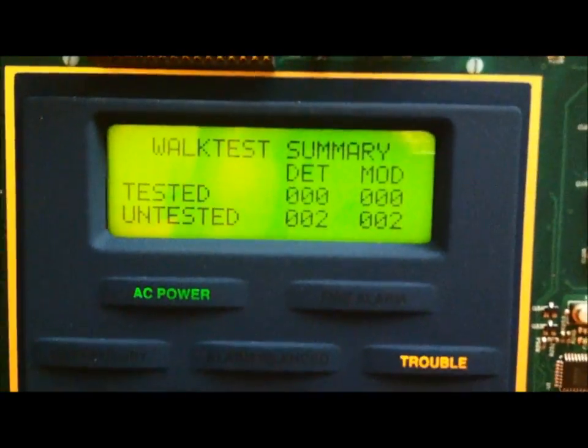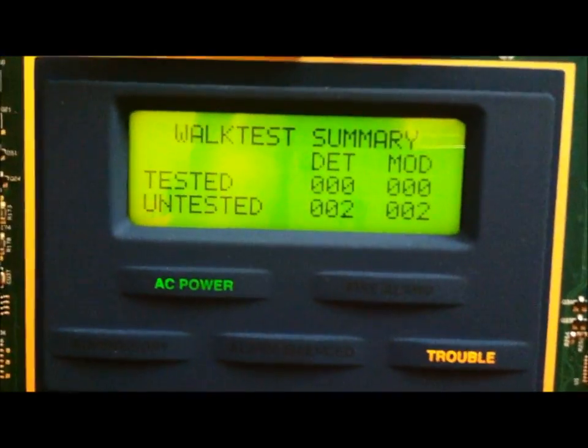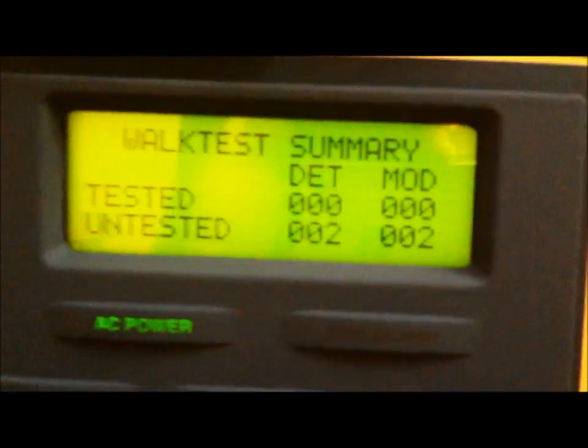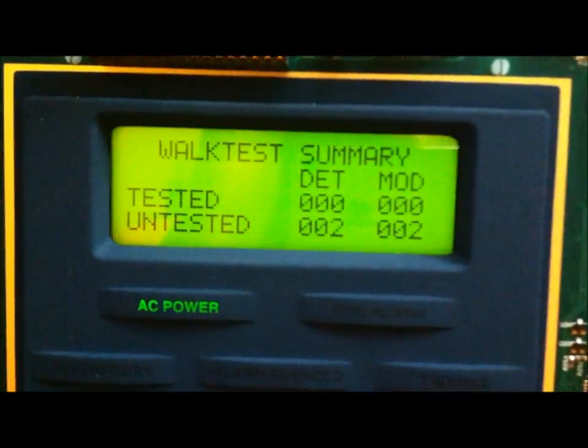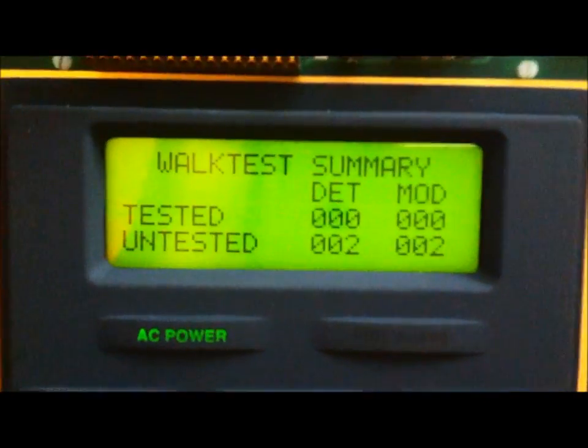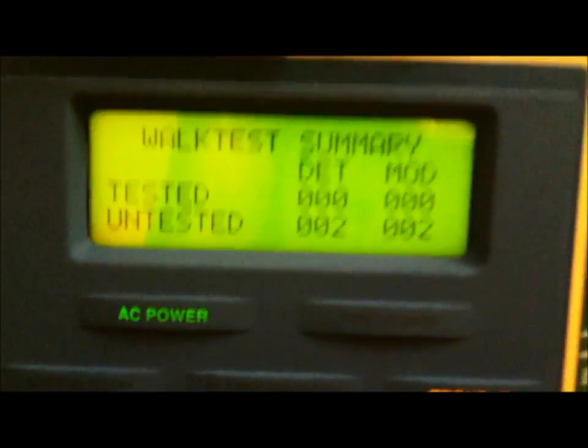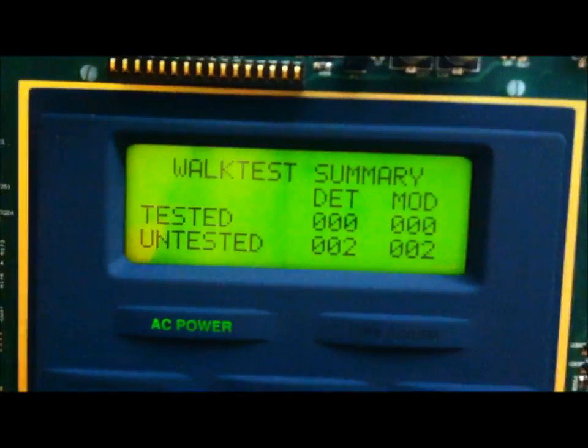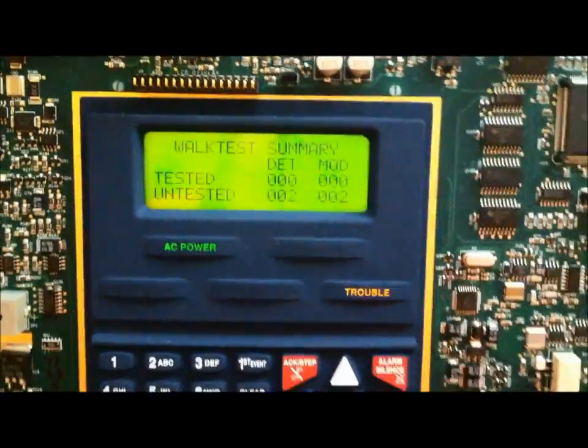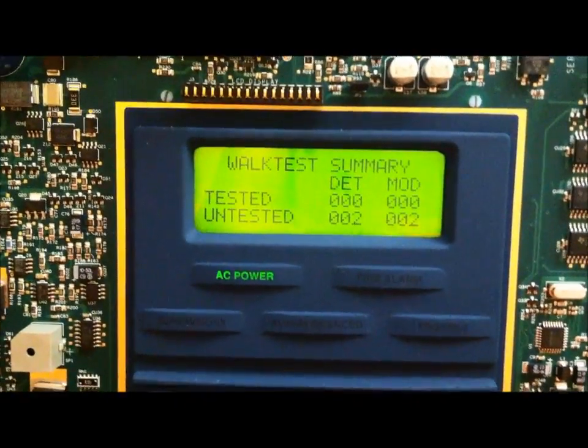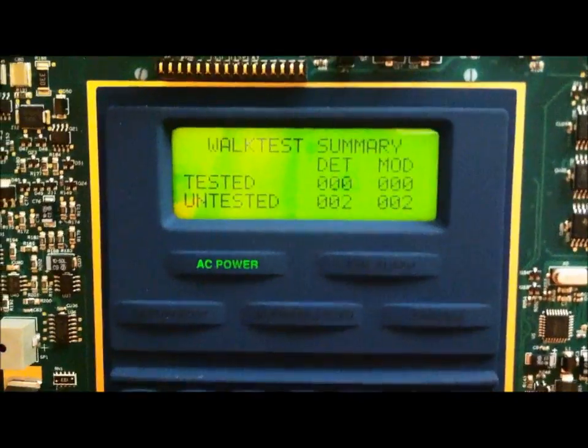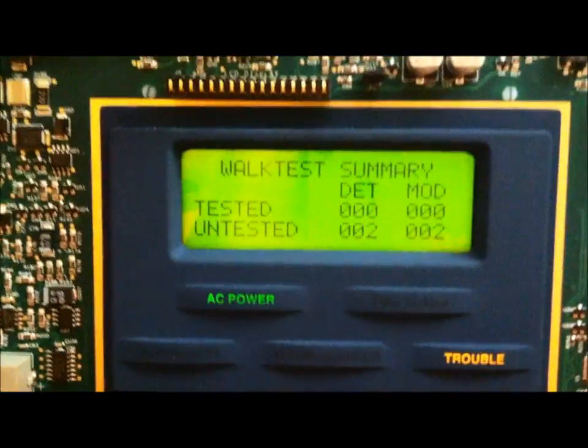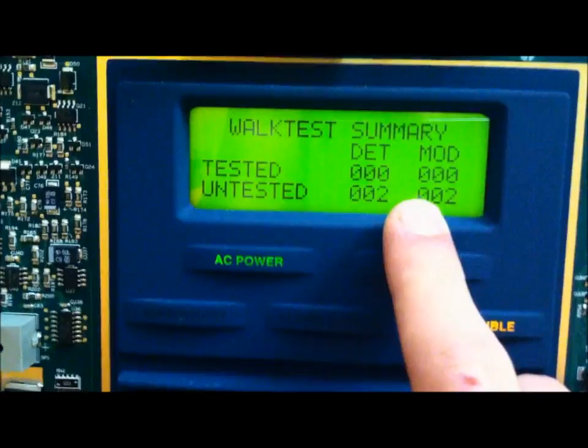This shows all of the devices. I have two pull stations, which is coming up as the monitor module, MOD, and then two detectors. If I were to activate one of the pull stations, it would say tested, and then one. One is not the device's address, it is just the amount of monitor modules that have been tested. So, if I were to test both smoke detectors, it would come up as two tested, zero untested.